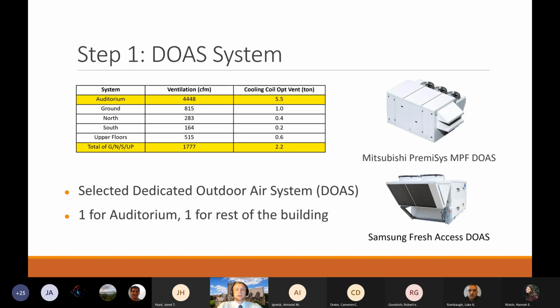So we did this for each of our different cooling systems, and from the results, we determined that we would need 1 DOAS unit to support the auditorium and 1 to support the rest of the building. We selected the larger Mitsubishi model, which could handle up to 5,000 CFM for the auditorium, and the smaller Samsung model, which could handle up to 2,000 CFM for the rest of the building.